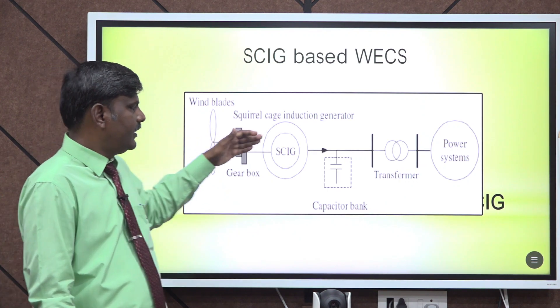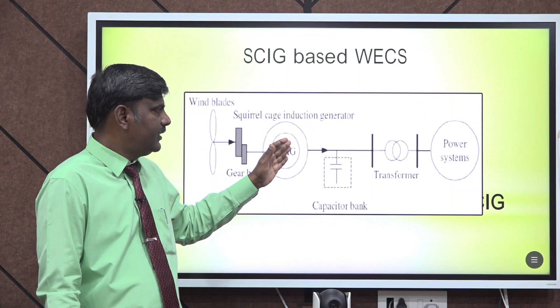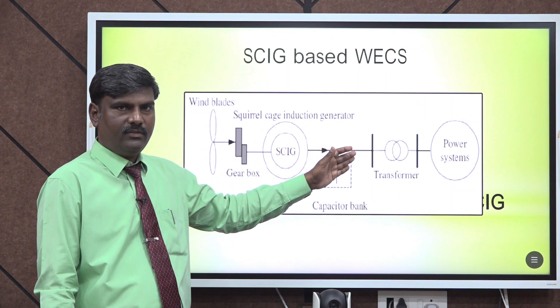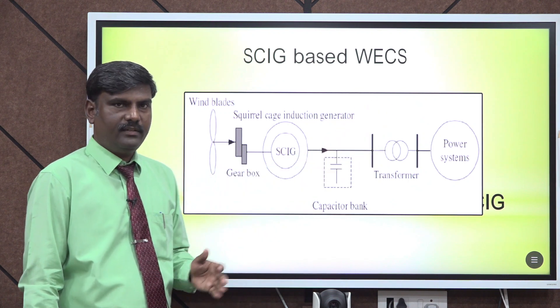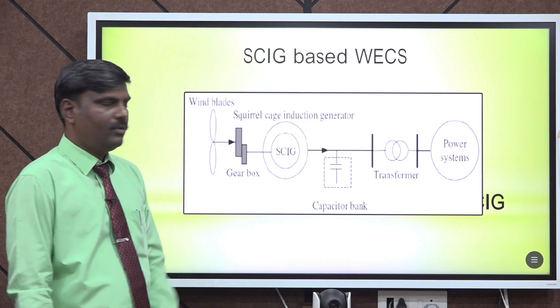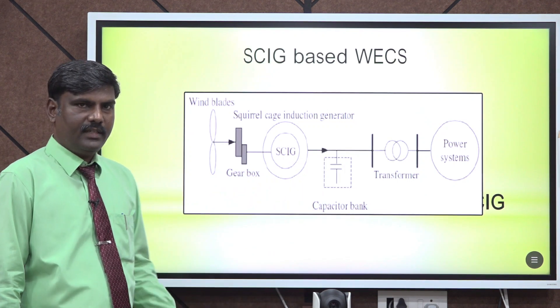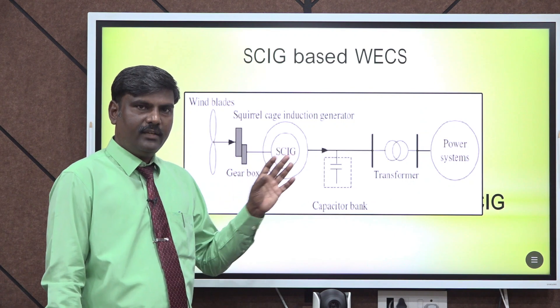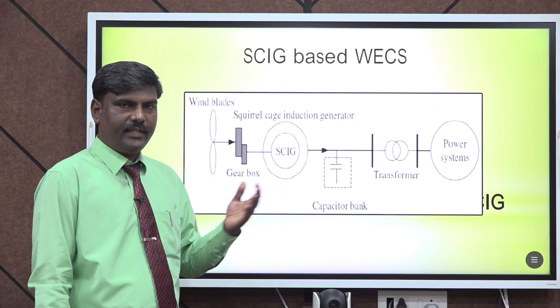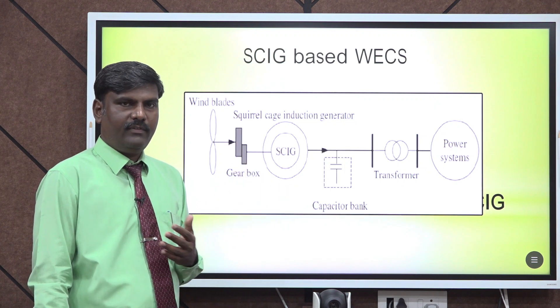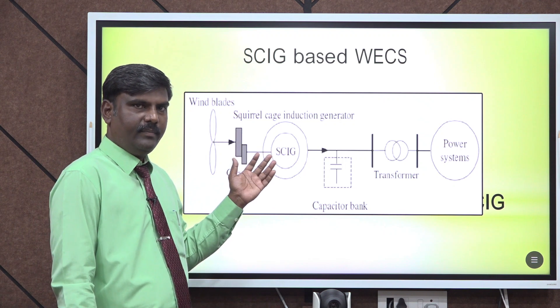From the squirrel cage induction generator, the electrical terminals are connected to a transformer, and from the transformer it is fed to the power system, that is the grid. For this squirrel cage induction generator, we need a capacitor bank because the squirrel cage induction motor operates at a lagging power factor, so a reactive current requirement will be there.